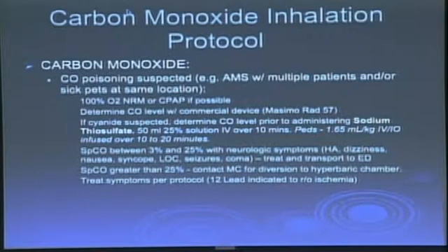If you really have a CO level of 25, you should have lots of symptoms. So a person who has no symptoms, and your machine says they've got a CO level of 30, there's something wrong. That person should be unconscious. That person should be, at the very least, complaining of a severe headache, vomiting, total dizziness, and you just have to admit, what makes it inaccurate?